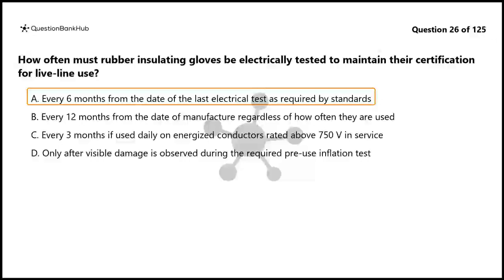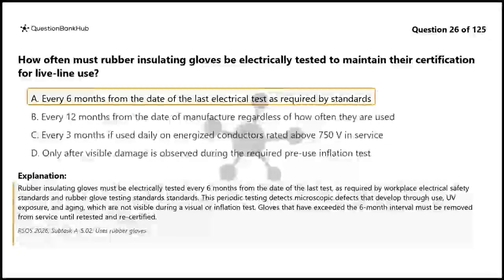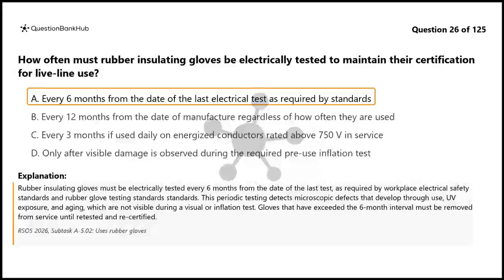The correct answer is A. Rubber insulating gloves must be electrically tested every 6 months from the date of the last test, as required by Workplace Electrical Safety Standards and Rubber Glove Testing standards. This periodic testing detects microscopic defects that develop through use, UV exposure, and aging, which are not visible during a visual or inflation test. Gloves that have exceeded the 6-month interval must be removed from service until retested and recertified.